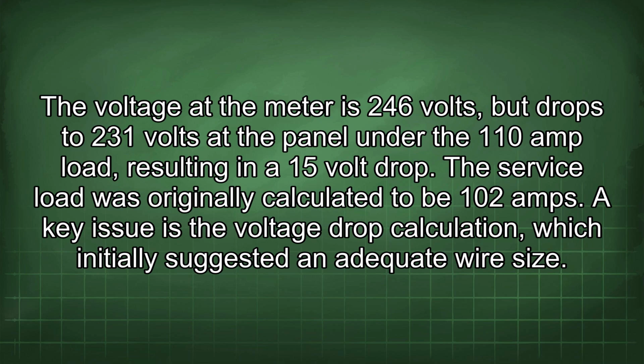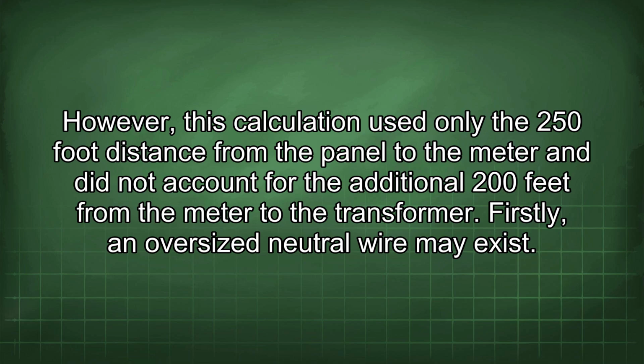The service load was originally calculated to be 102 amps. A key issue is the voltage drop calculation, which initially suggested an adequate wire size. However, this calculation used only the 250-foot distance from the panel to the meter and did not account for the additional 200 feet from the meter to the transformer.